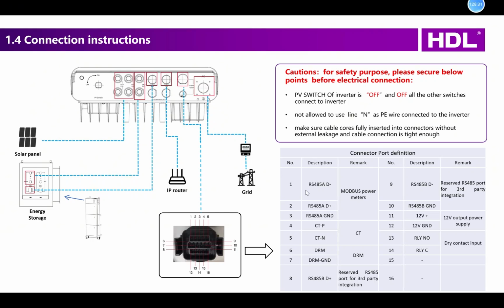And we already did integration with a specific brand, Chint. So you will also see the model number in the manuals, if you want to buy a Modbus power meter which is compatible with the HDL inverter. And here you can see that it has output for 12 voltage power supply and also for dry contact input.